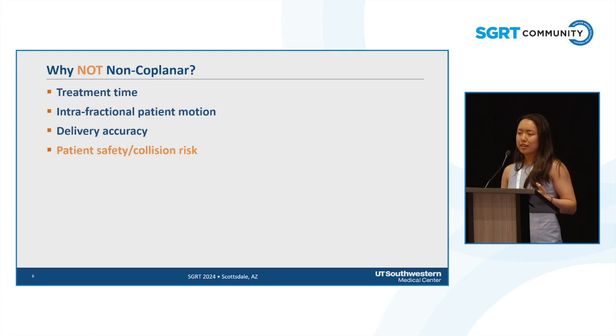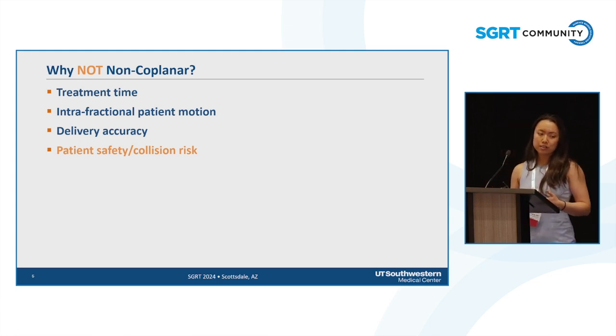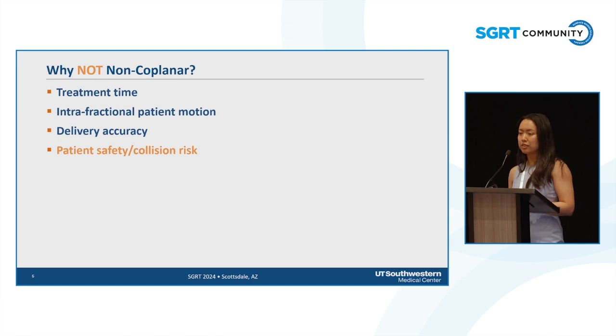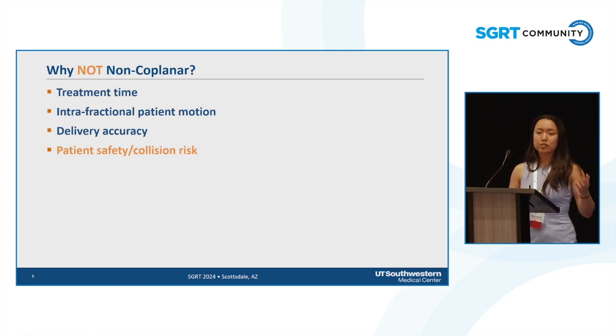So on the other side, why don't we see more non-coplanar treatments in the clinic? There are four main sticking points. The first is that with the increased complexity in treatments comes increased treatment time. And that corresponds to potentially increased intrafractional patient motion. And then the other thing that people are worried about is that with so many moving parts, there will potentially be a decrease in delivery accuracy. And last, but probably one of the more important sticking points, is that people are worried about patient safety and the potential collision risk.